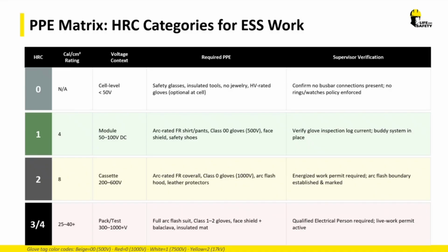So for electrical work inside a control panel, panel board, switch gear, or something like that, a lot of it's the same PPE for the most part. We're navigating hazards that are direct current, DC current, and the voltage rating of the glove is matched with that. For shock protection, the glove is your shock protection, but gloves don't have much for arc flash protection. I'll tell you right now, that's where a lot of people get it wrong, they choose the wrong glove. They look at it and say 'oh, it says arc flash glove,' yeah that's an arc flash glove, but that's not a voltage rated glove. You can't use that glove to work on electrical equipment. It's only to put inside a boundary that has arc ratings, so it doesn't work well for that.